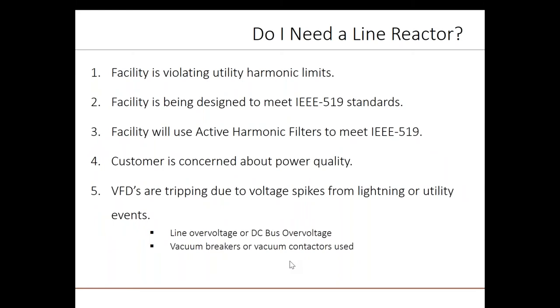Here are some situations where a line reactor can be beneficial. Firstly, if the facility is violating harmonic limits set by the utility, and punitive action may be threatened, line reactors will provide some harmonic mitigation. If there are a lot of non-linear loads like VFDs, then line reactors alone will not likely achieve IEEE 519 compliance. Further steps, like active harmonic filtering or passive harmonic filters, may be needed.